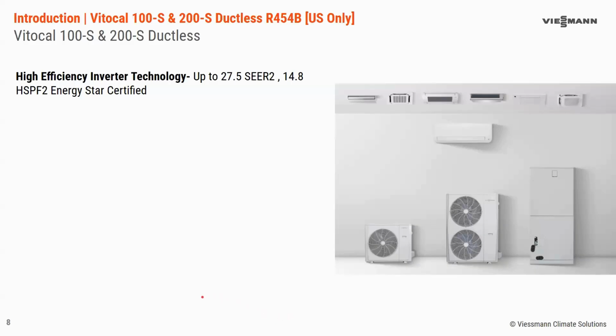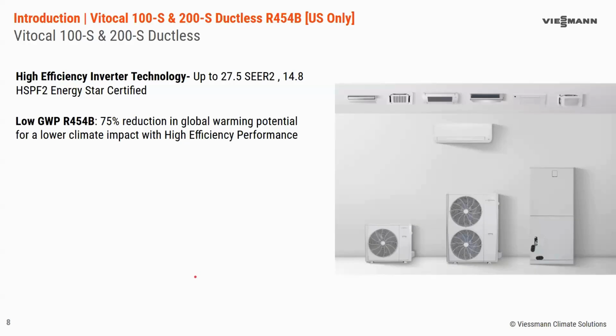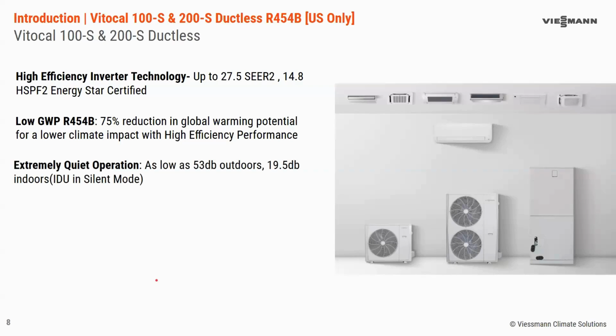So we're seeing upwards of 27 plus SEER2. We have Energy Star certifications, cold climate ratings. All of that is possible through the inverter technology of these systems. Along with the high efficiency performance, the refrigerant itself is a high efficiency and low impact refrigerant, the new R454B refrigerant. It offers a 75% reduction in global warming potential versus the outgoing refrigerant with similar performance specifications. So same great performance, less impact on the environment.